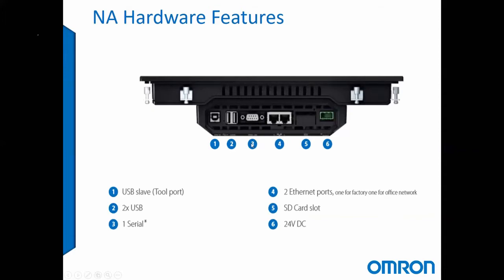Next to that, we've got a 232 port, a serial port. We don't talk to PLCs with this port, but we can code some drivers to read data from a barcode reader, stuff like that. It's not too commonly used. Our new PLCs don't come with serial on board, so Ethernet's kind of the way of the future with Omron, and we're just keeping serial there just in case, I think. To the right of that, we've got 2 Ethernet ports. So we can set these up to pass traffic through, or we can have these completely independent, isolated networks.